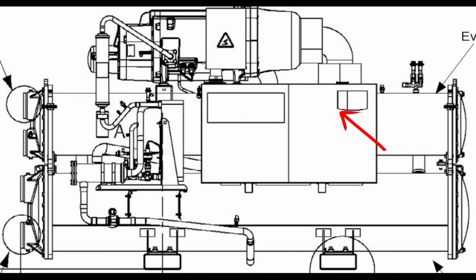So when we scale that back over to the schematic here, now let's actually just look at this machine in its entirety. It's very similar to the old school screws we've always been used to with these Carriers. They're not that different. There are a few modifications that I see here, but we've got our condenser down here. We've got our evaporator up here. I know this is the evaporator because my suction line is coming off of this top barrel into the compressor. Our control cabinet is right here. Right? We can see we have a brazed plate economizer.